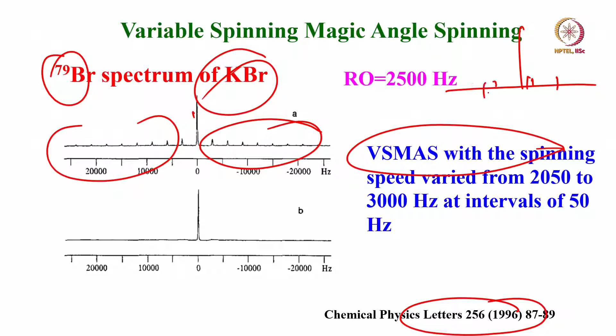What you will do is, every time you acquire the signal, you vary the spinning speed. For example, once I acquire the signal at this spinning speed, I get a spinning sideband. The second time I acquire, what will happen to the central band? That remains the same, and it gets added up, whereas the next time the sideband appears at a different place because the spinning speed is different. Again I acquire once more, I change the speed, the central band is again added up, and the sideband moves away. So every time I keep changing the spinning speed and keep acquiring the signal, the central band keeps adding up and sidebands keep on moving away. So if you acquire for a long duration, because of signal averaging, the central band will grow and all the sidebands get suppressed.